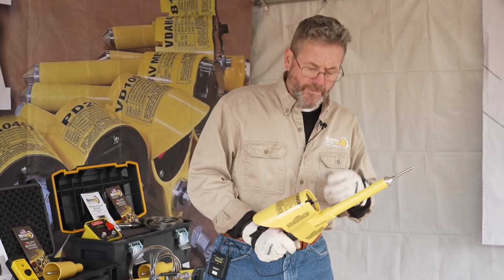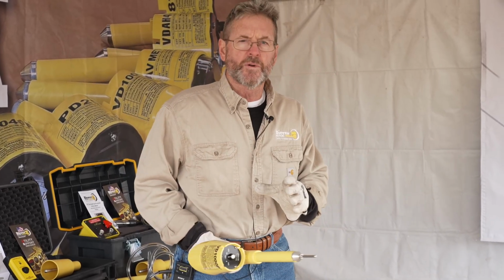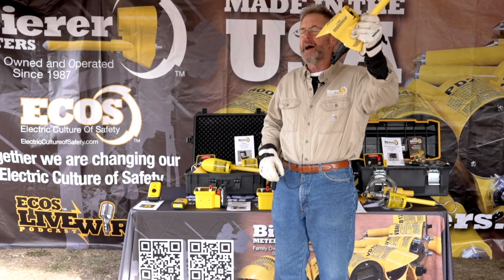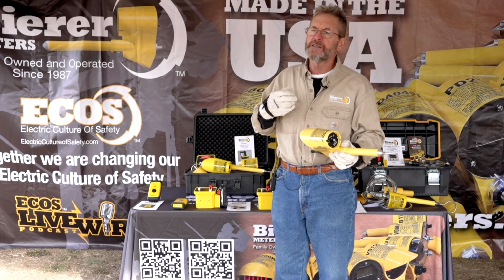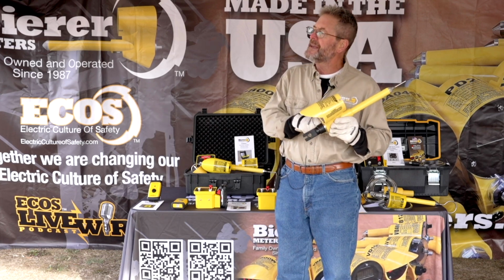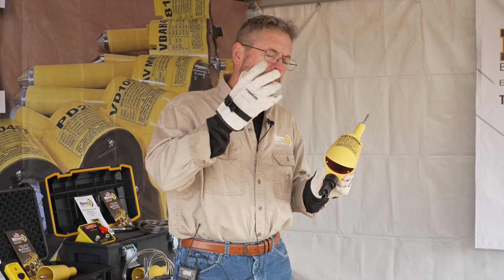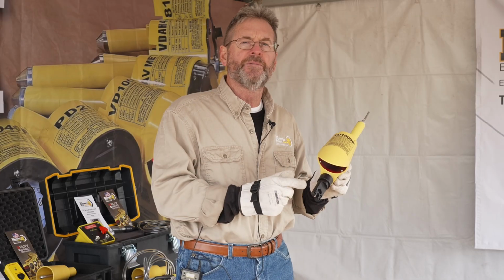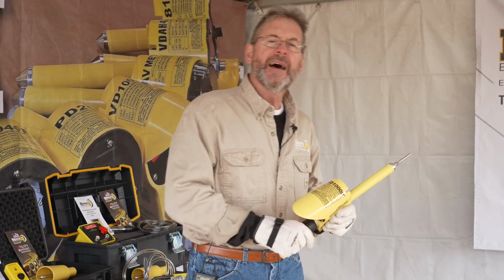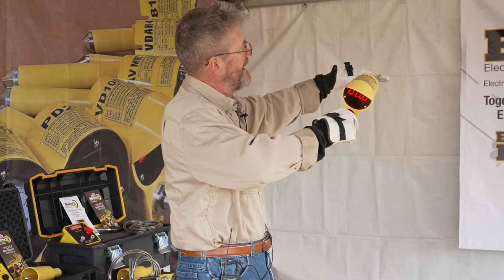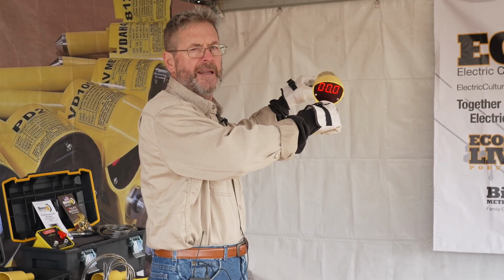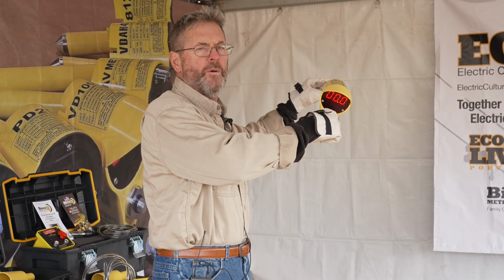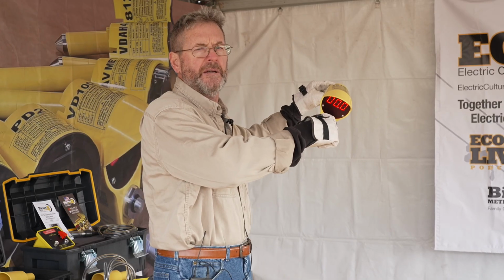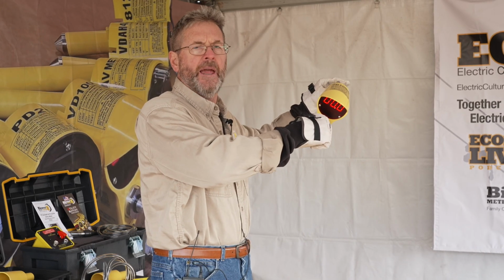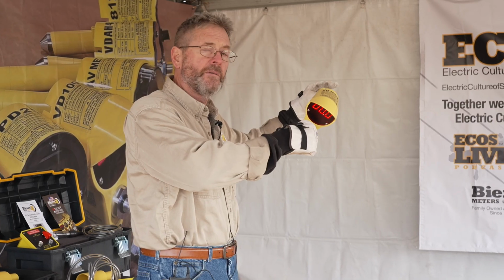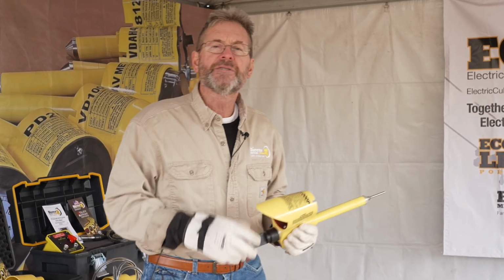So we know the tool's working on a live known voltage source. I prefer a live conductor personally, because I can verify that the tool is in calibration or not, so it's really important to test it first on a live known voltage source. Then we go to that line, that conductor, and make contact. As you can see, that conductor is de-energized, so there's no backfeed, no induction, and no system voltage, so you're verifying the tool is telling you the truth.